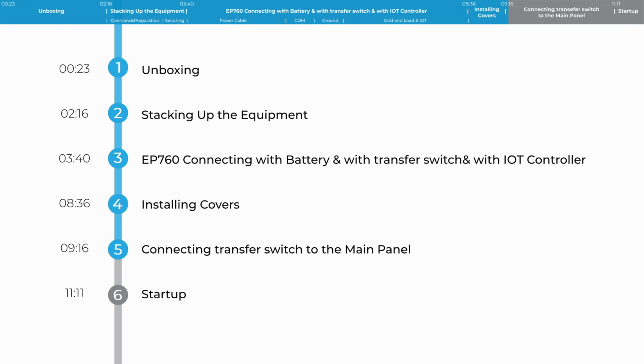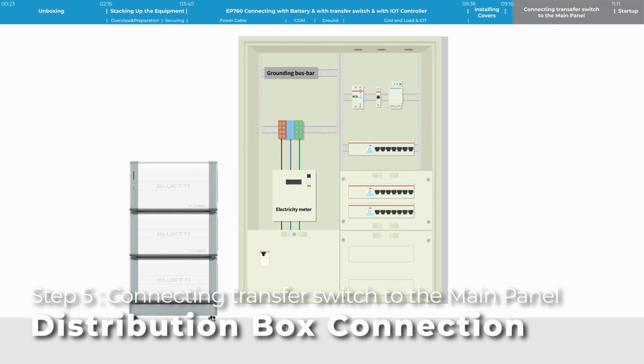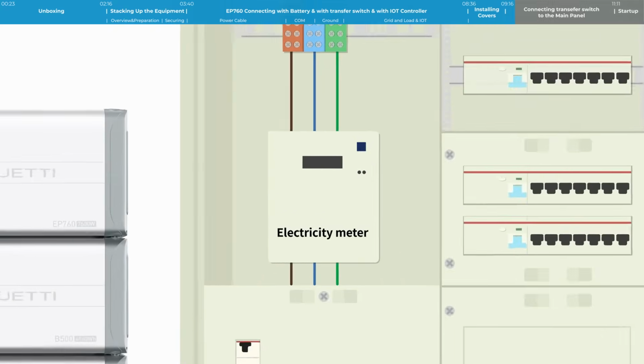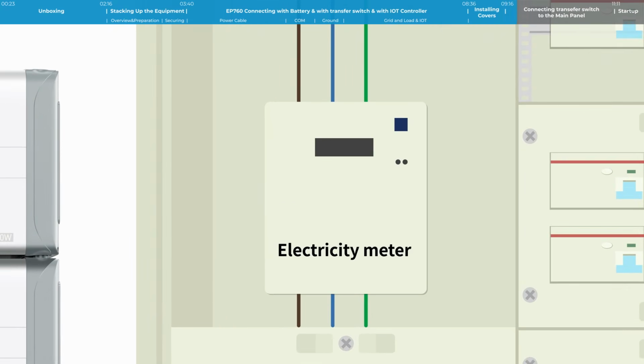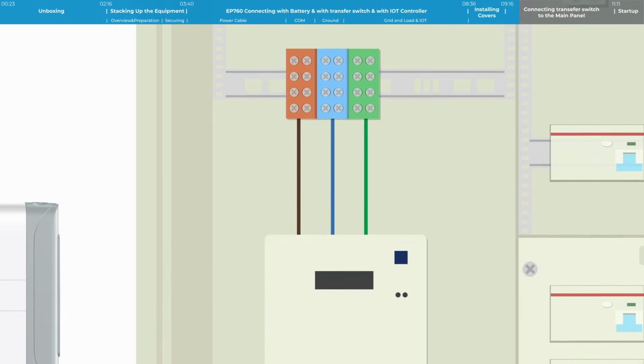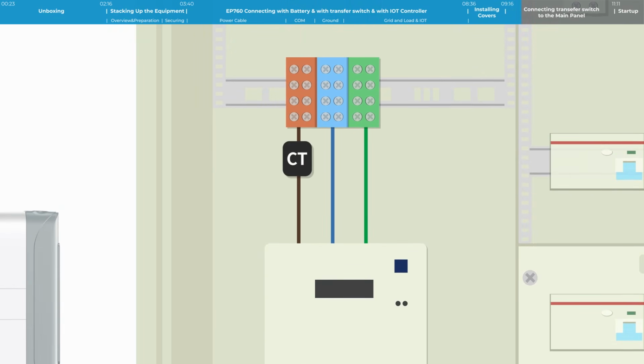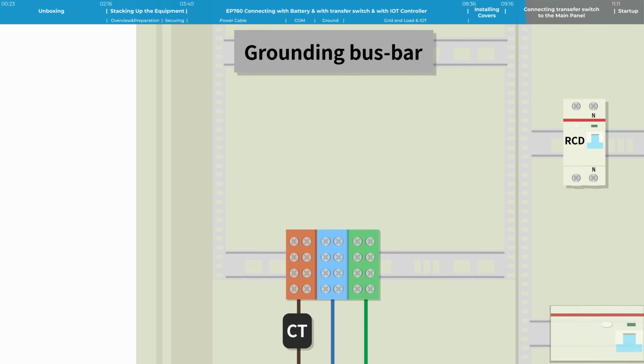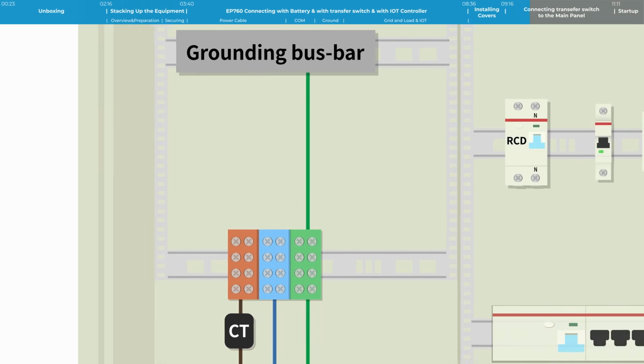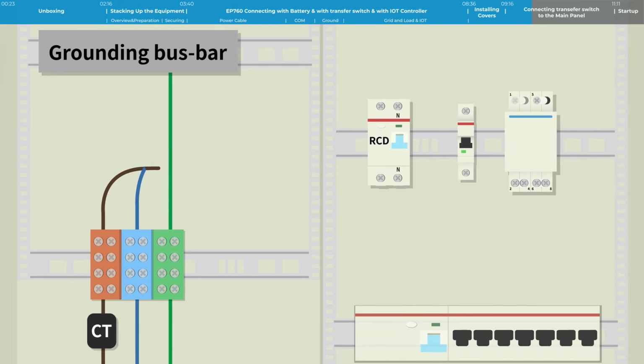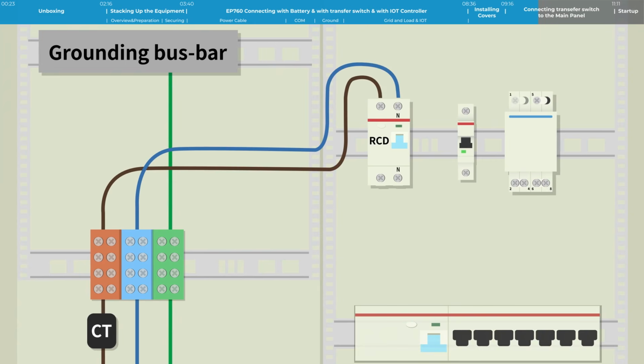Step 5. Connect the subpanel to the main panel. Firstly, find the electricity meter in the distribution box. Clamp the EP760's CT to one live wire of the main circuit. The arrow points to the grid. After that, find a terminal block on the circuit or somewhere around the bus bar. Connect to the terminals of the 2P RCD, residual current device, with one live wire and one neutral wire. The sequence from left to right is L, N.